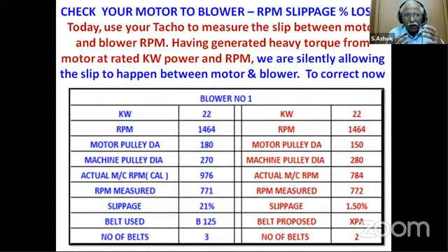A typical motor to blower with V-belts, where all the drive is taken on a belt. In an IT building at Chennai, we found almost 20% loss. We are trying to achieve a part load efficiency, kilowatt per ton, from 1.5 to almost 0.5 to 0.7 kilowatt per ton.